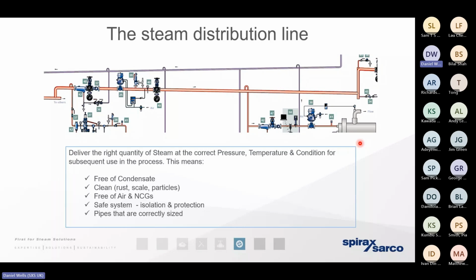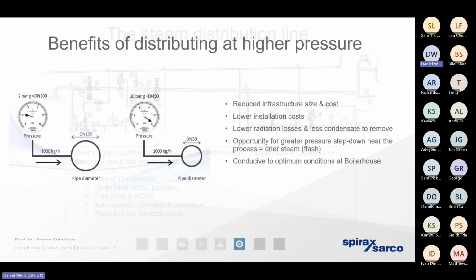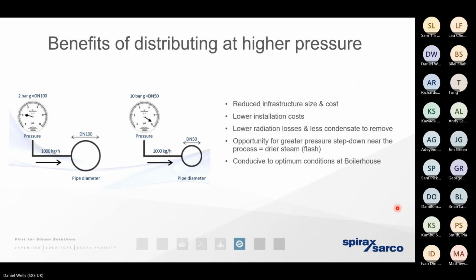Some of those items of capital equipment will require periodic maintenance. So it's vitally important that we make provision for being able to isolate them safely. And then we also need to ensure that the pipework itself has been correctly sized. Remember, with the steam system, we don't pump steam. Unlike a water-based system, it can only move in accordance with the pressure drop around the infrastructure. So it's vitally important that we size those pipes correctly.